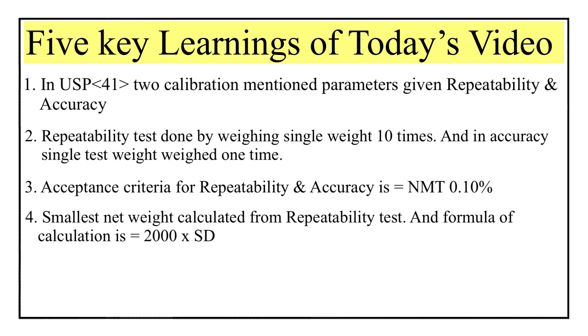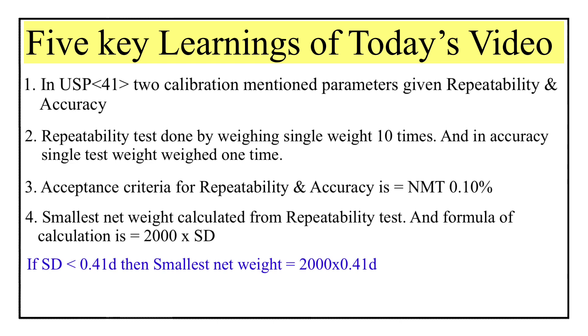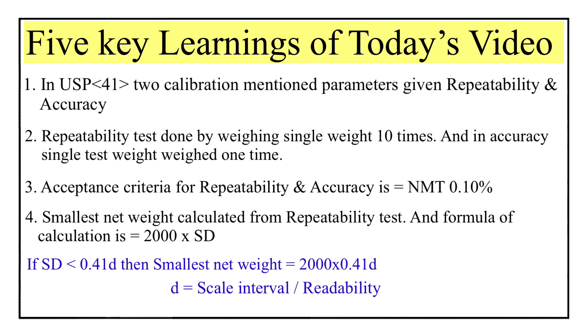Point four: smallest net weight is calculated from the repeatability test and the formula is smallest net weight = 2000 × standard deviation, where standard deviation is obtained from the repeatability test. If the standard deviation value is less than 0.41d, then the formula becomes 2000 × 0.41d, where d is called the scale interval or readability — this tells you the minimum value a balance can read.